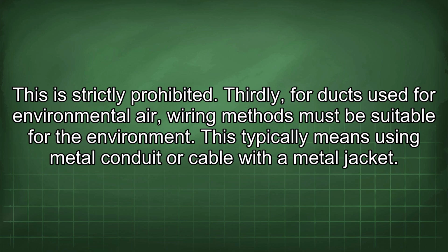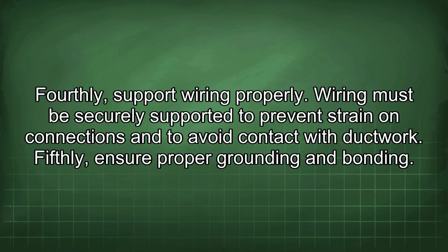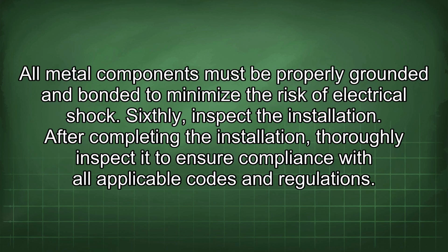This typically means using metal conduit or cable with a metal jacket. Fourthly, support wiring properly. Wiring must be securely supported to prevent strain on connections and to avoid contact with ductwork. Fifthly, ensure proper grounding and bonding. All metal components must be properly grounded and bonded to minimize the risk of electrical shock.